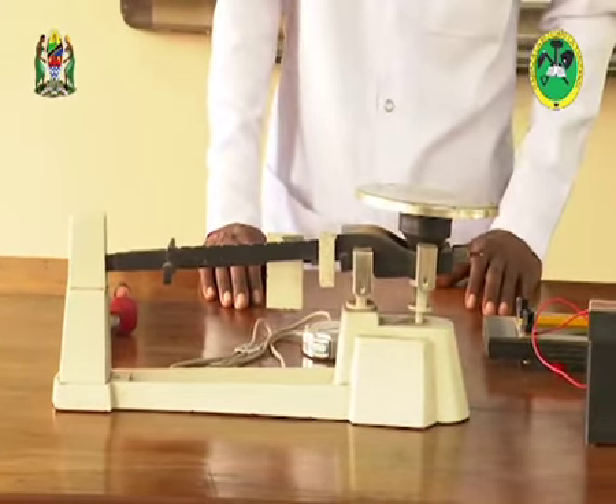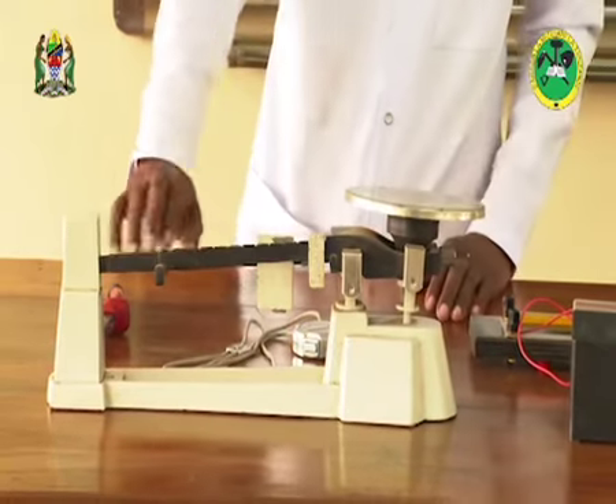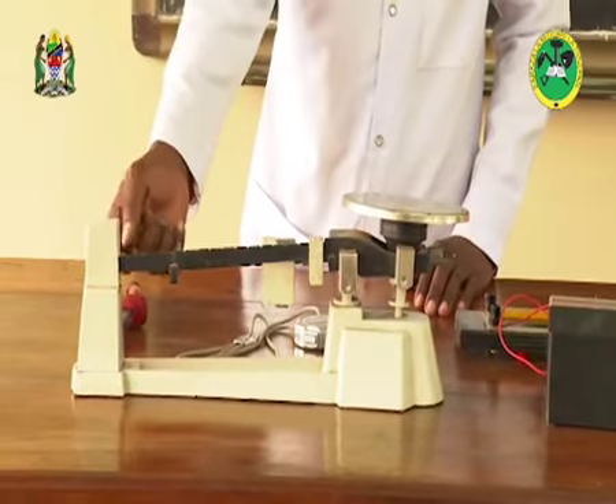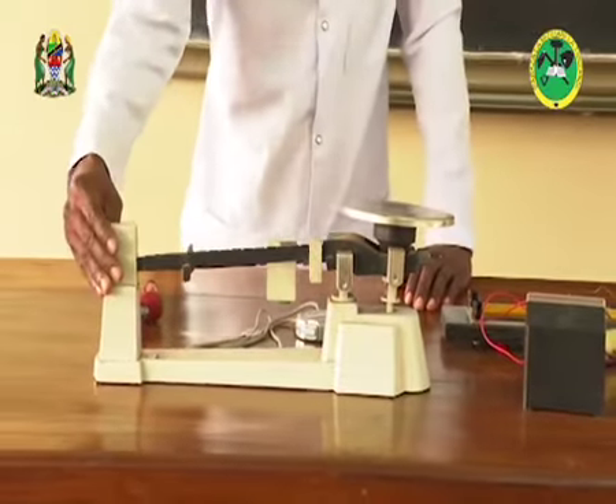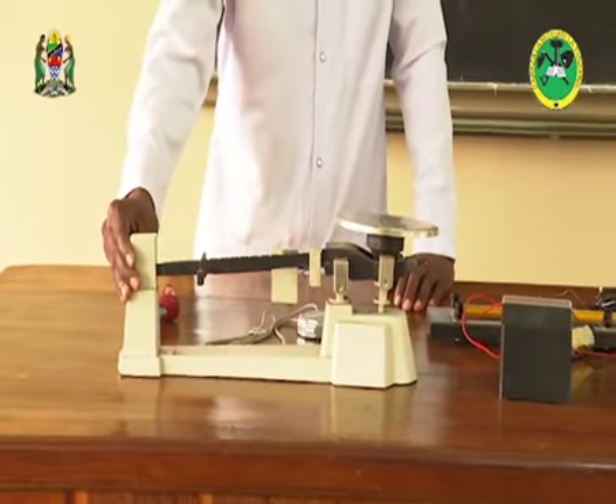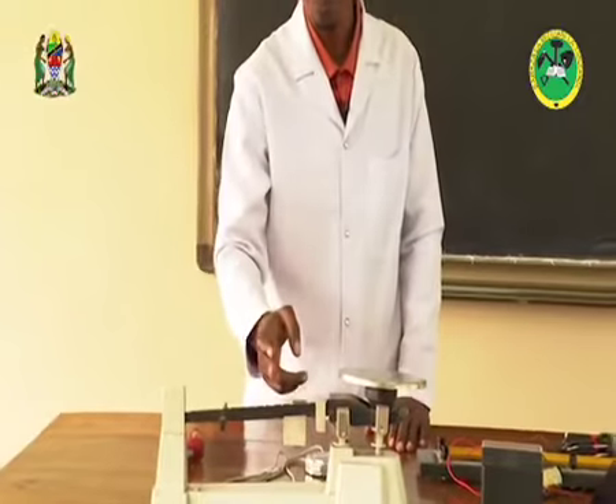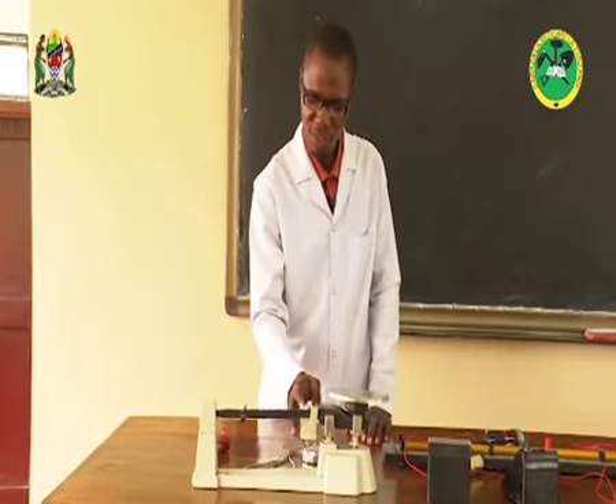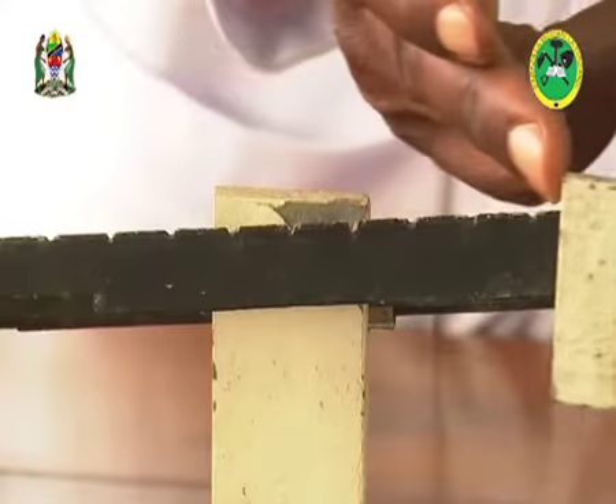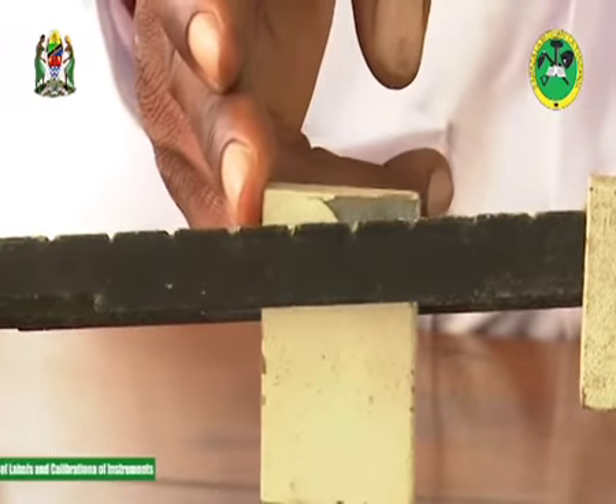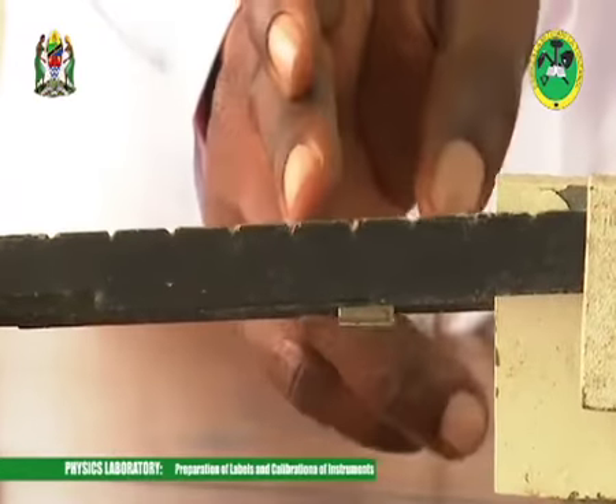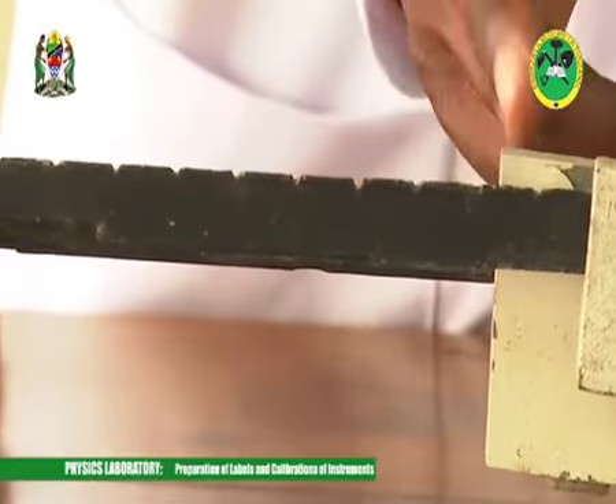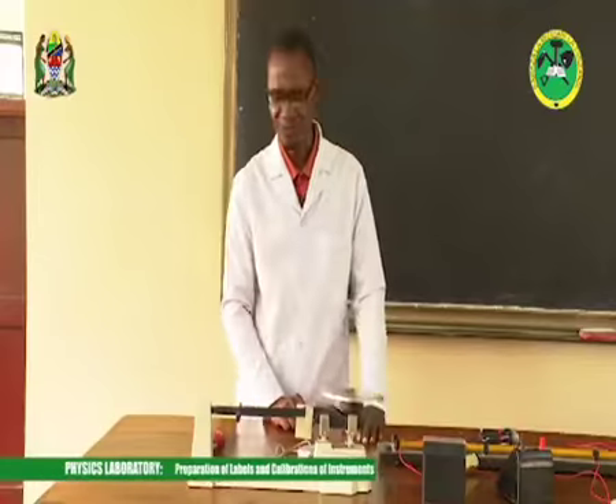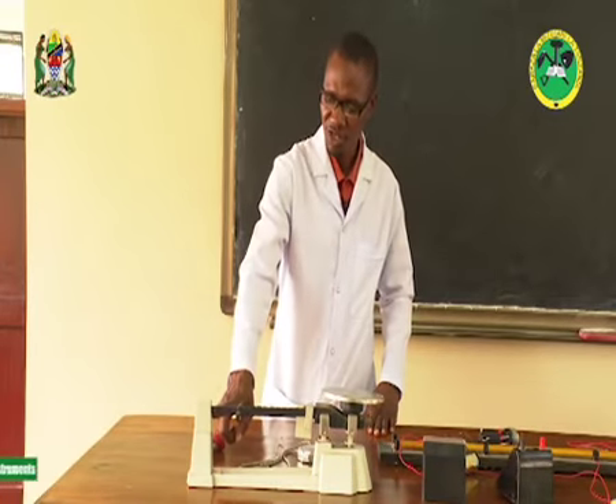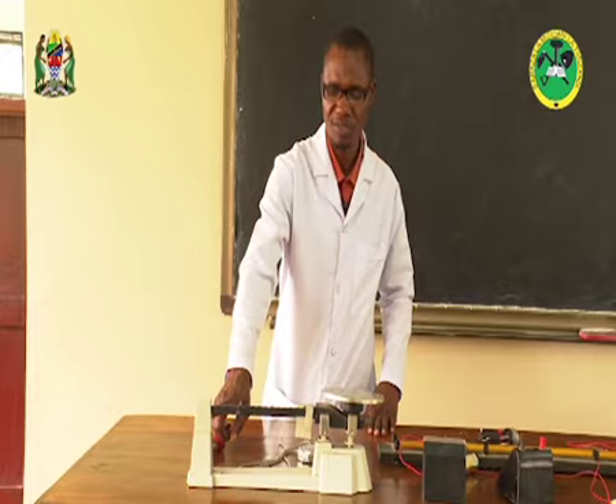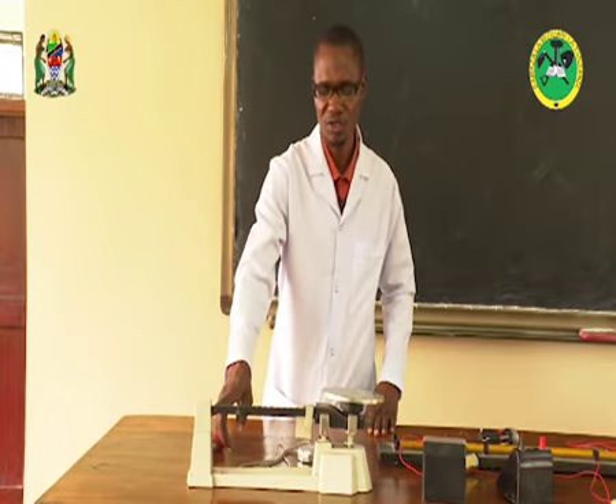Now, how do we calibrate this? The balance has a mark which should always be pointing to the 0 mark here at the rear side of this balance. So the first aspect is to put all the slides at the 0 position. This one, the range of 0 to 100 grams, should be at the 0 position, and the range of 0 to 500 grams should also be at 0, and the lowest one also should be at 0. Now check whether this mark is always pointing at the 0 position, just like other meters. This is what you need to assess.